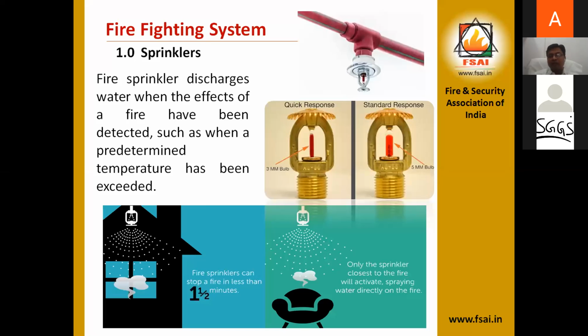There are two types of sprinkler, quick response and standard response. The only difference is the bulb thickness. In quick response, the thickness of the bulb is 3 mm, and in standard response, the thickness is 5 mm. So the 3 mm bulb starts sprinkling earlier, and the 5 mm bulb starts sprinkling later. Fire sprinklers can stop a fire in less than 1.5 minutes. Only the sprinkler closest to the fire will activate, spraying water directly on the fire. So though we have provided n number of sprinklers in the building, all sprinklers will not be activated at a single time. They activate only in the area where the fire has occurred.